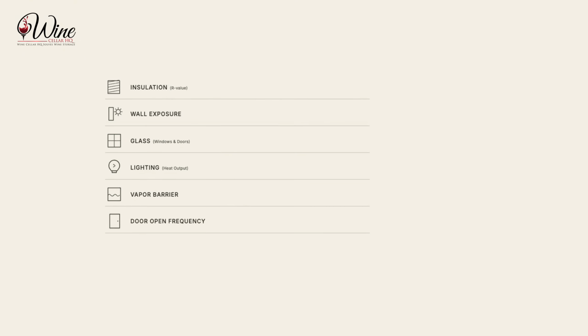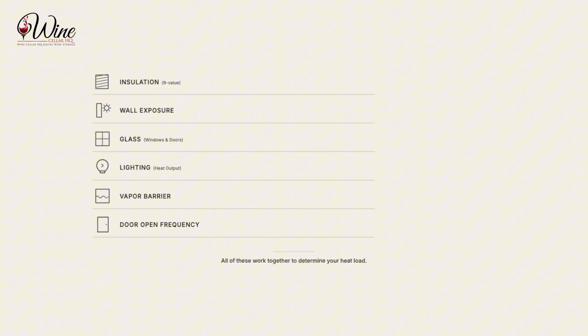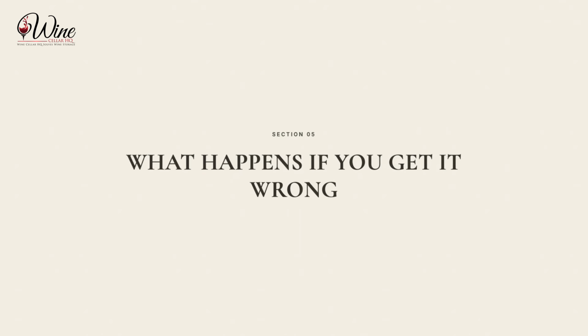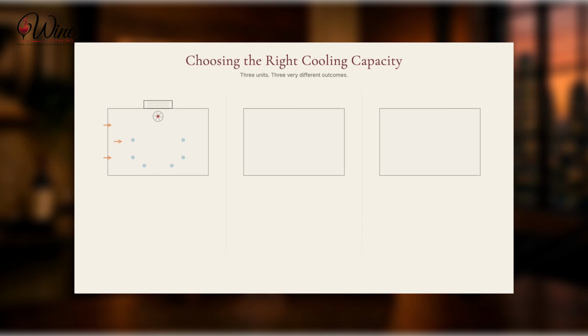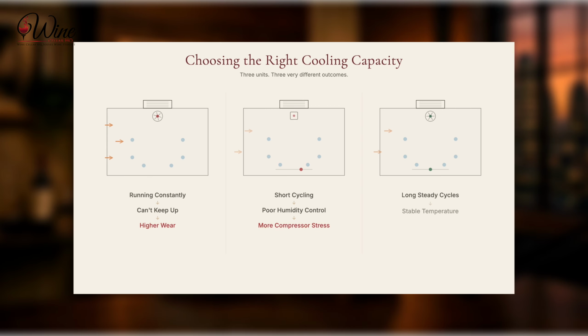Put all of that together: dimensions, insulation, exposure, glass, lighting, vapor barrier, and usage, and that's what produces an actual accurate BTU per hour number. Everything else is just a guess dressed up as a number. An undersized unit runs constantly, never quite catches up, and wears out early. An oversized unit has the opposite problem. It short cycles, switching on and off rapidly, which actually hurts humidity control and stresses the compressor too. The right-sized unit runs long, steady cycles. That's what actually protects your wine and your equipment long term.